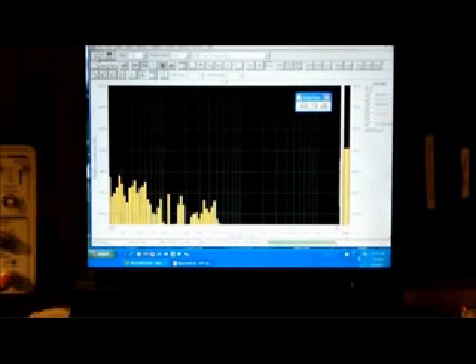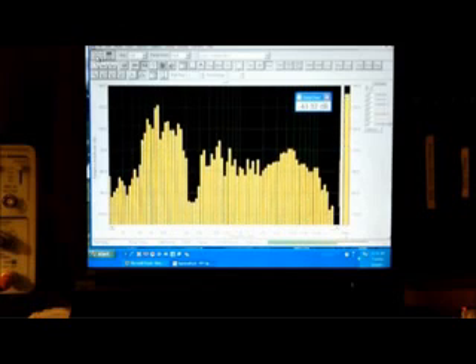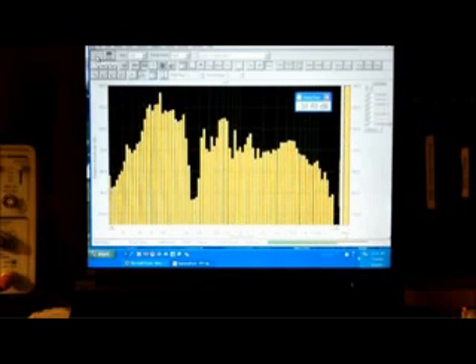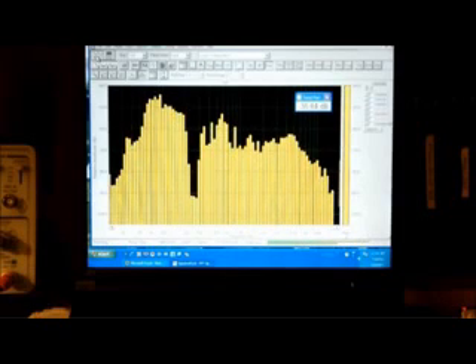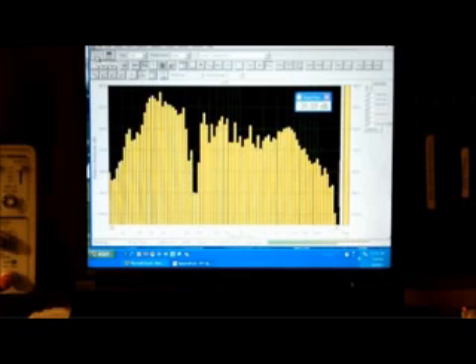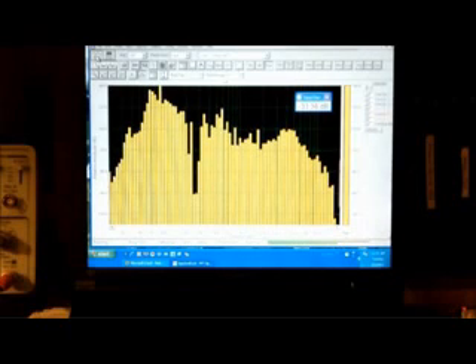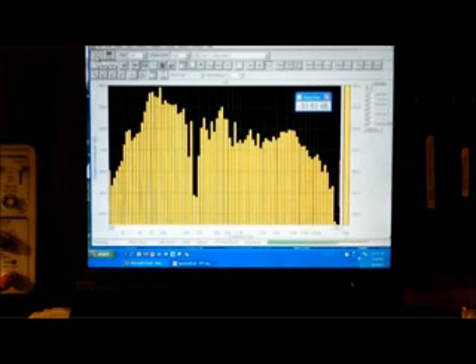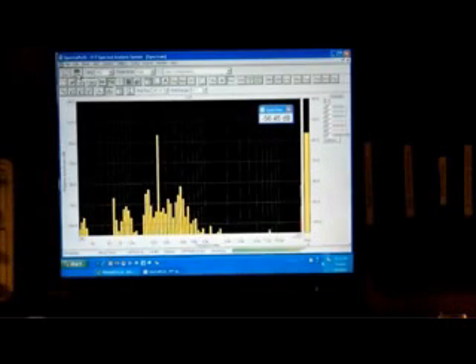There you can see we're looking at the spectrum analysis, and I start the excitation signal. You can see that there's a hole in the spectrum somewhere in the 200 Hertz range, and now I can bring up the probe tone, which you can see there. So the idea here is to make sure that the excitation signal does not leak into that hole in the spectrum in any significant way, so that the probe signal can accurately measure any change in volume. I'm going to turn on the stimulus, which will give a measured SPL in the dead ear of about 114 dB SPL.